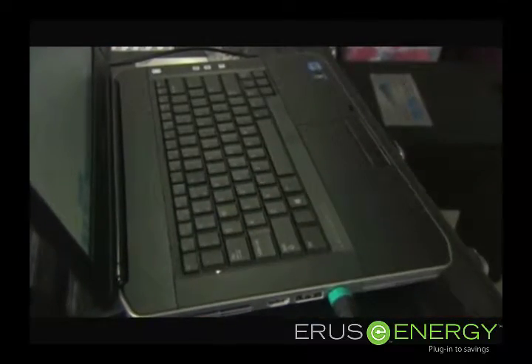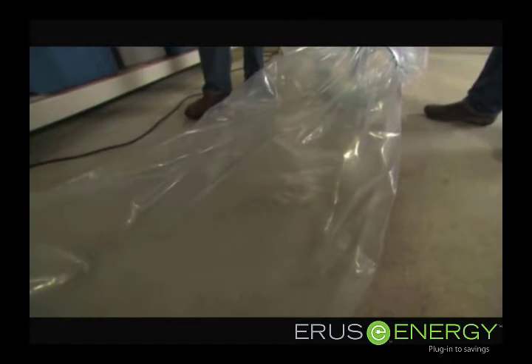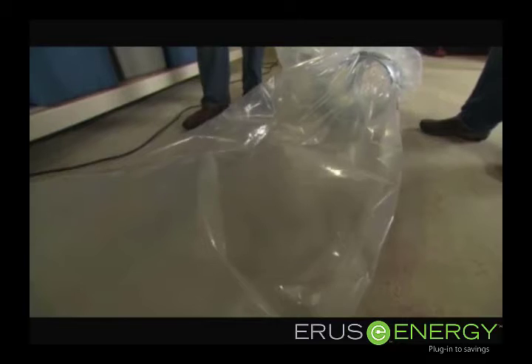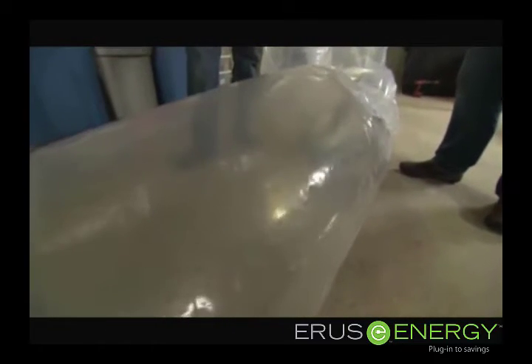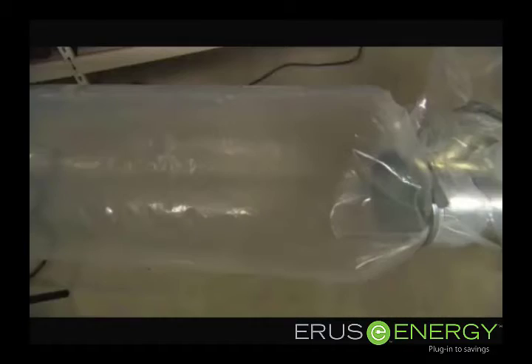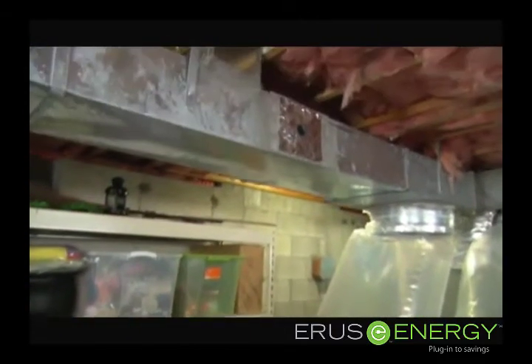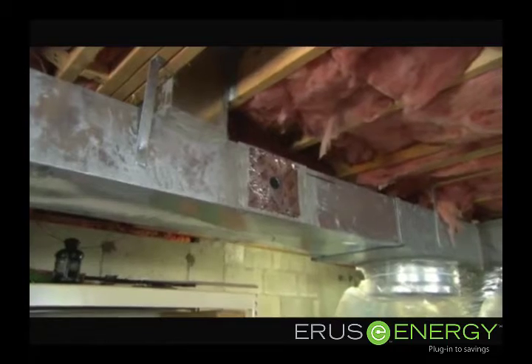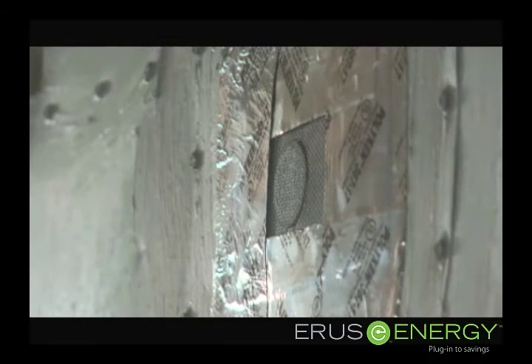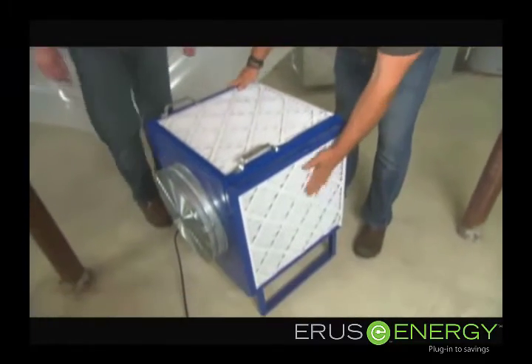So we'll activate the machine. Okay. The fan will turn on, and it'll start to inject the sealant. Here it comes. Right now, the airborne sealant is flowing through the pressurized ductwork, and it's squeezing out just where they have an opening in the ductwork. As it flows through those little cracks, it catches on the crack and actually coagulates to seal any duct leakage. Now, any of the sealant that happens to leak into the living space can be captured from this scrubber fan onto the filters.